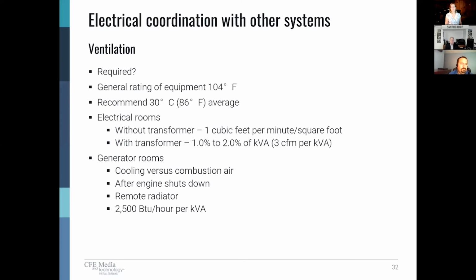You have to look at how those louvers are opened and closed. You want to look at the cold or hot climate, and when those come on, you certainly in a minus 10 degree Fahrenheit don't want to open up initially all the dampers. You might want to phase them open so you don't get all the cold air coming in and freezing the room down before the engine heats up. And a general rule of thumb is that an engine generator will put off about 2,500 BTU per hour per kVA. These are terms that are helpful to discuss with your mechanical engineer. Next.